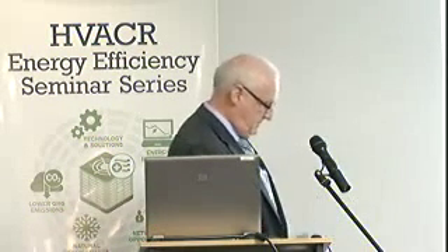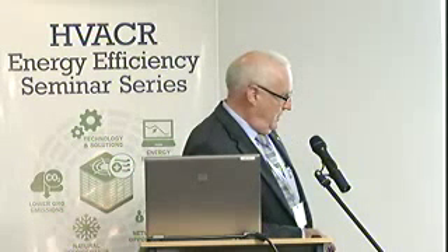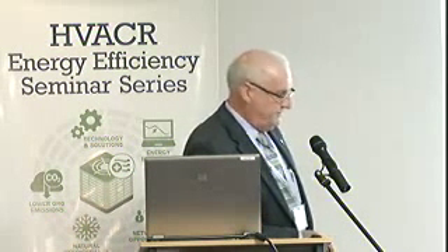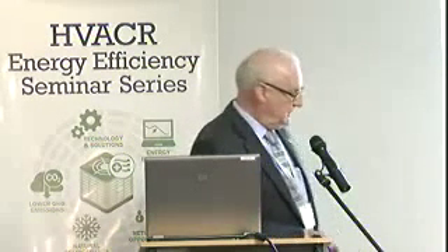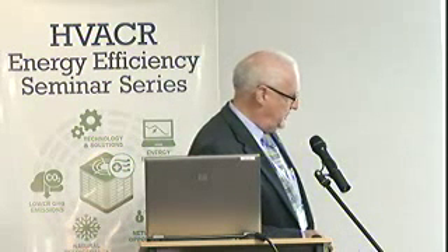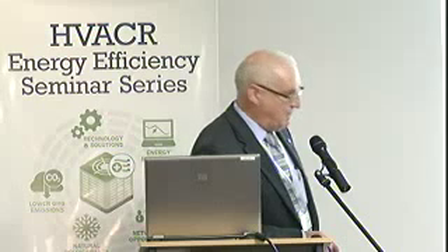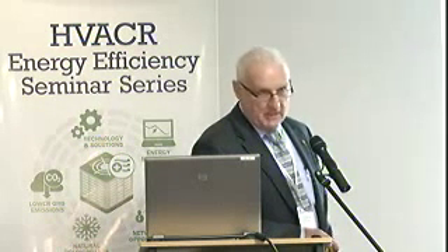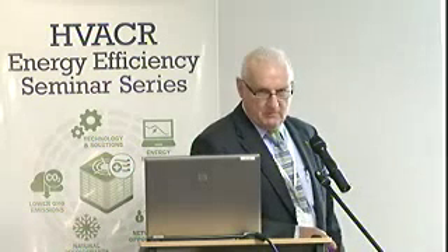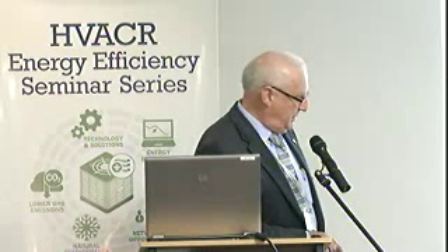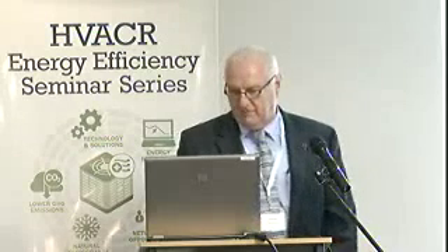Now VPO, the same input, current lagging the voltage. By its nature, and we'd have to go through vector analysis, but it's because the VPO works best on the inductive loads. So it's actually allowing this lagging current to catch up a bit, not entirely. And you heard Sam say that they've seen up to 20% improvement in power factor by implementing voltage optimisation. But what we're doing is we're actually reducing the voltage waveform. So you can see here we've reduced the amplitude. We will also reduce the current to some degree, but they are a different thing and they do it in a different way.